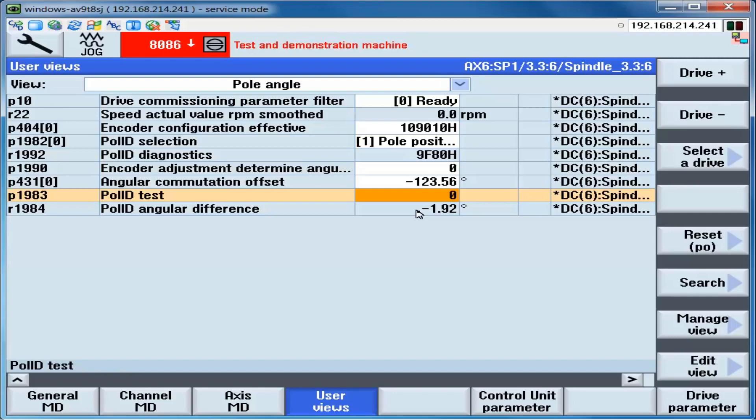We'll check a few spots here as a demonstration. We make P1983 01, press enter, and we get a pole angle value here in R1984. We rotate the motor to another spot and we make P1983 01 and R1984 reads out another value. Record the value, move to another spot, and test again.